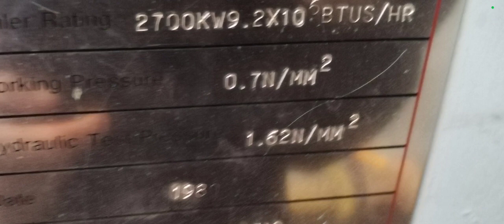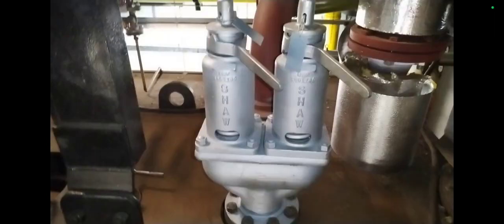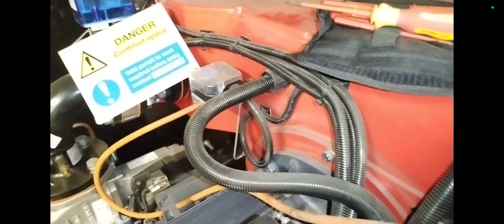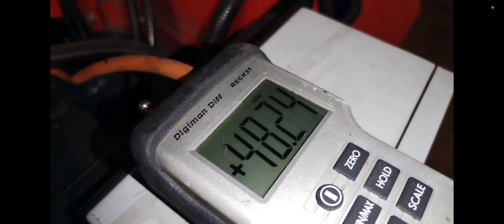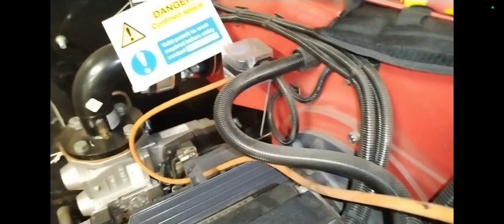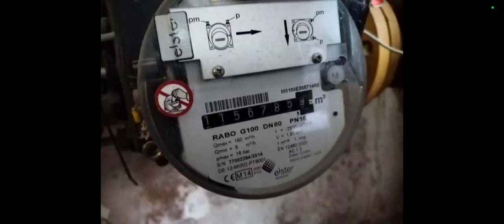A little connecting tube goes through there and comes to the other side. Made in 1980 — it can handle up to 2700 kilowatts. This is one of its gaskets. This is the back of the boiler above it — PRV set to about 6 bar — some valves there. There's our flue. Now I'm checking the air whilst the unit is on.